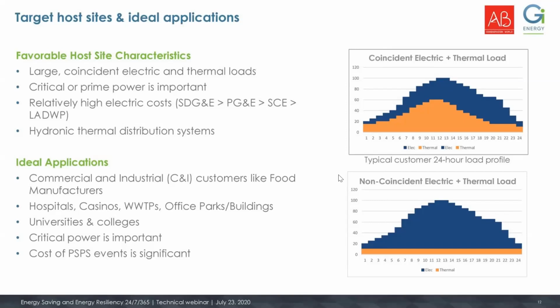If we have good thermal loads, we're able to size the facility on an optimum balance and truly maximize the value of the asset. Without good thermal loads, it becomes more difficult to extract value from a cogen plant, and the business plan suffers a little. Of course, we have executed projects that can still pencil out if electricity prices from the grid are very high, despite low thermal recovery - case in point, if the cogen unit is driven by additional value, for example through avoided outages.